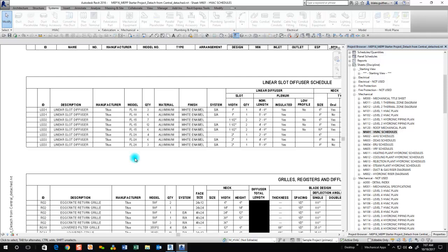I personally have looked at a lot of shop drawings for GRDs, and I've always wanted a more performance-based schedule that's showing me quantities and sizes of everything that I've modeled. I think it does a big favor to the contractor and the essentially sales rep pricing out everything, but also it helps us to review and really quantify what's in the model. So we're kind of moving away from this world of hiding our quantities because our model is what it is, so what's there to hide? If we missed a grill, then we missed a grill. It's not showing up on the plans either.